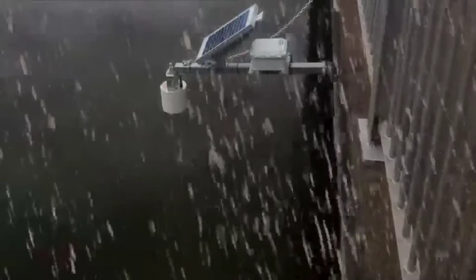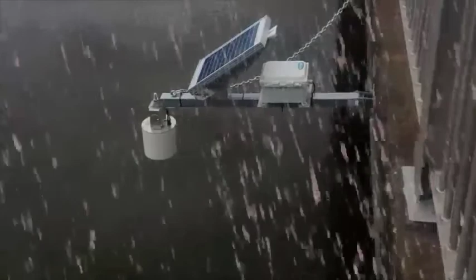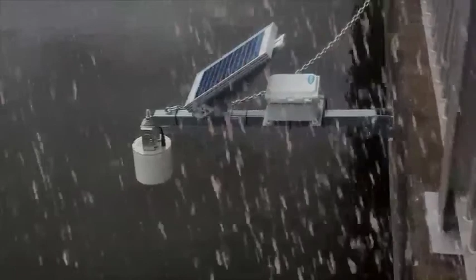Another thing that can happen is the cone may get covered by oil or dust or paint, which will prevent the signal output from the sensor. It may also happen that after the installation of the radar or ultrasonic sensor, some new development has happened near the bridge which is covering the water surface in that area. Or some big rock has travelled with flood water force and is sitting under the radar or ultrasonic sensor. These obstructions will affect the data output. These are the general conditions of which one should be aware.